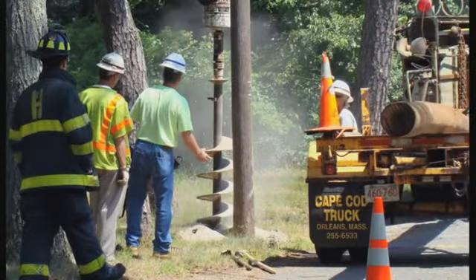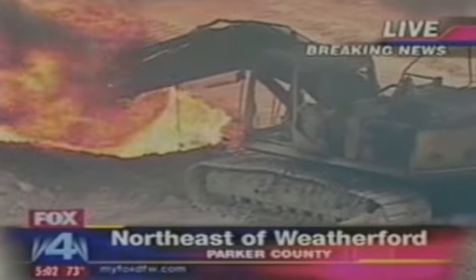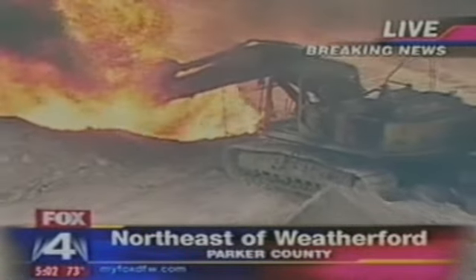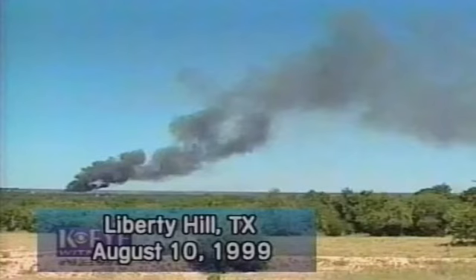Natural gas is lighter than air and is combustible in approximately a range of 5% on the low side and 15% on the high side. Natural gas liquids include propane, butane, combinations of propane and butane, ethylene, and other combustible products.